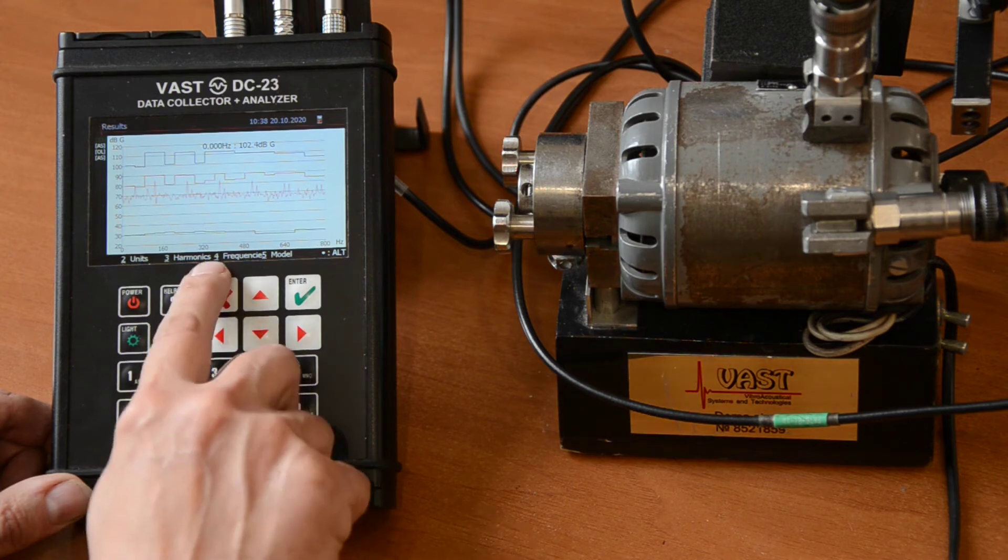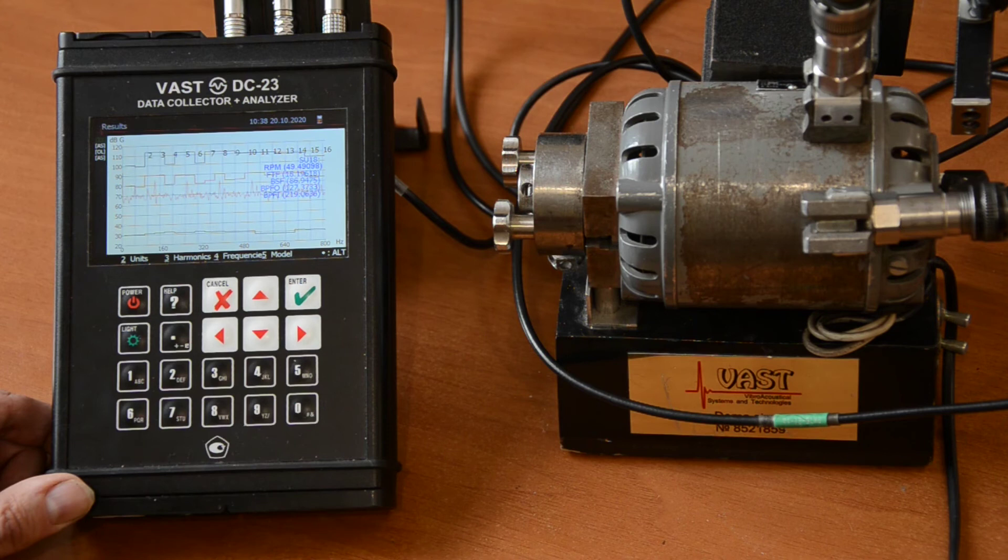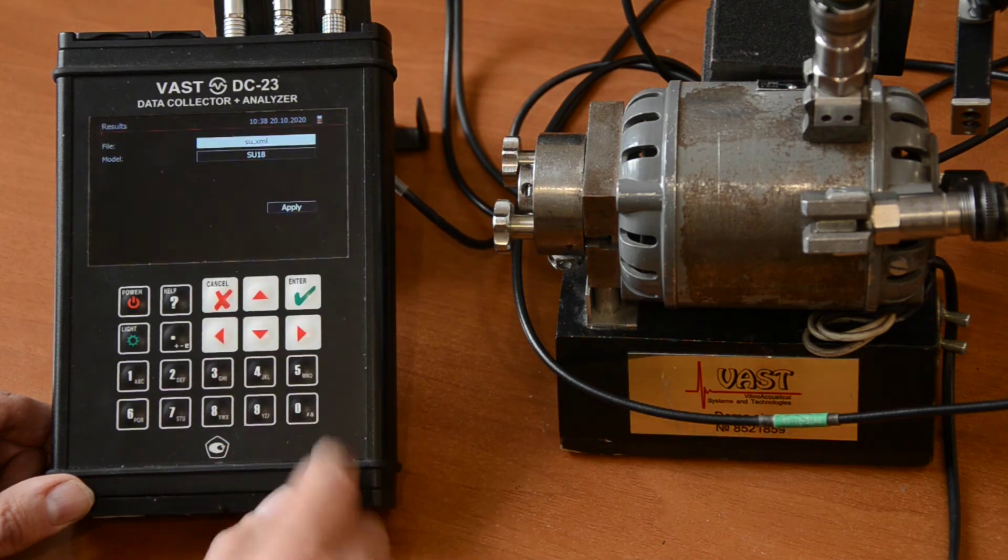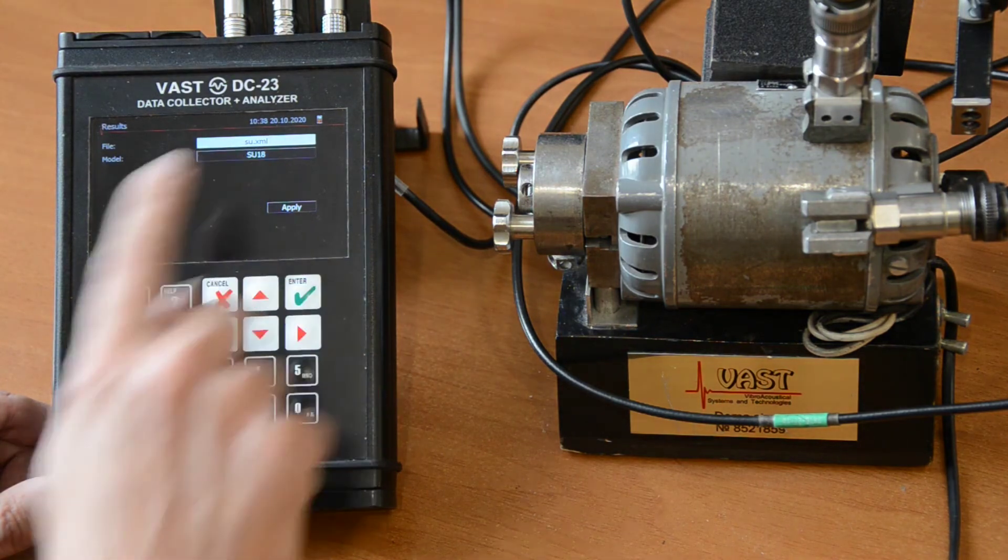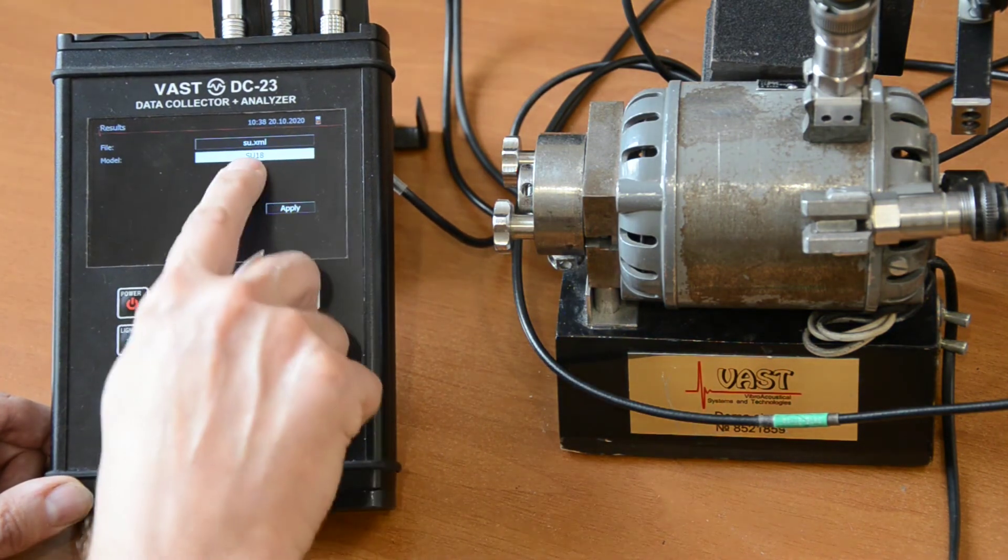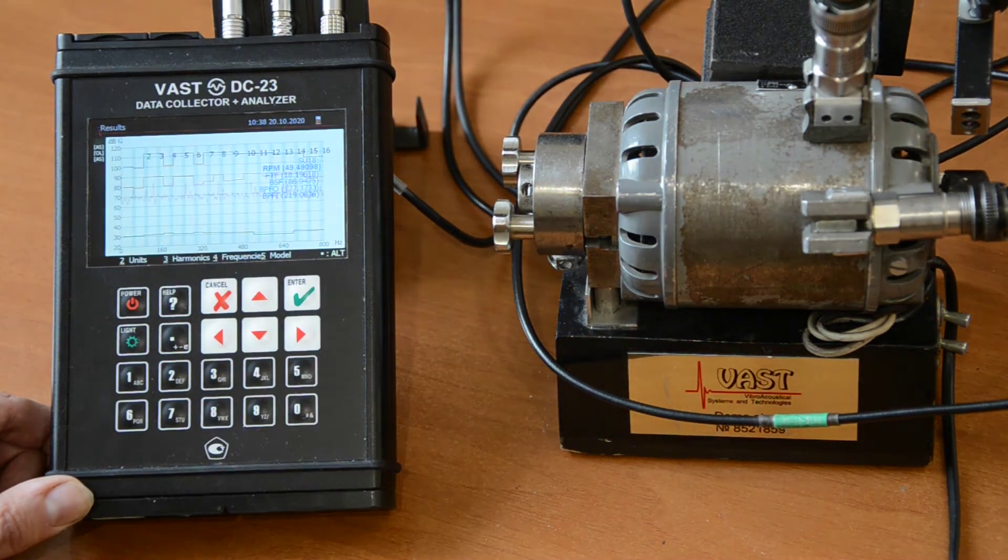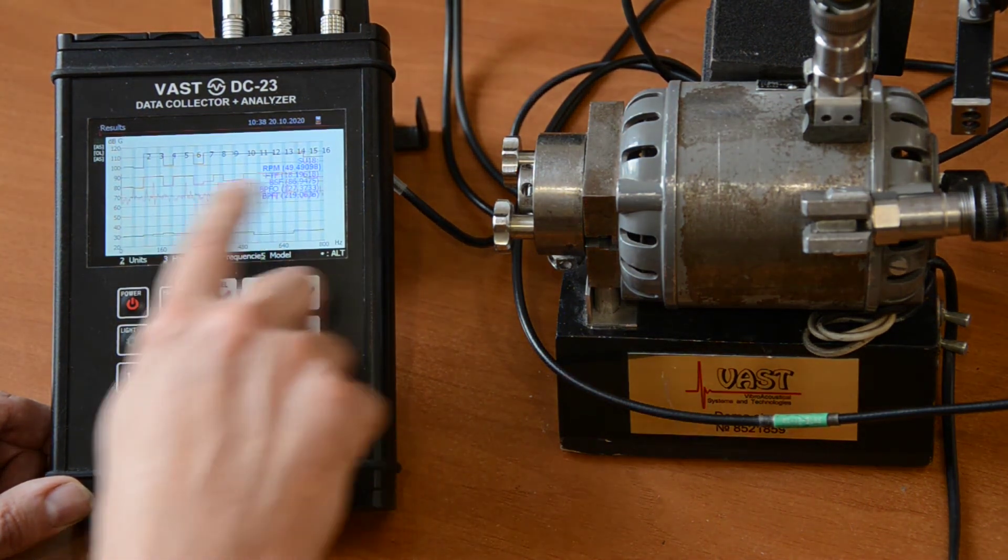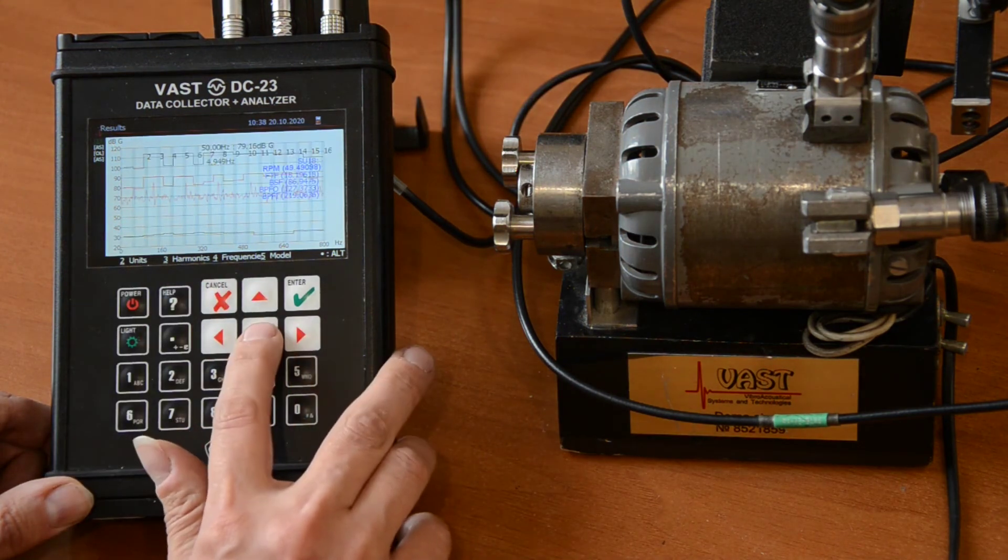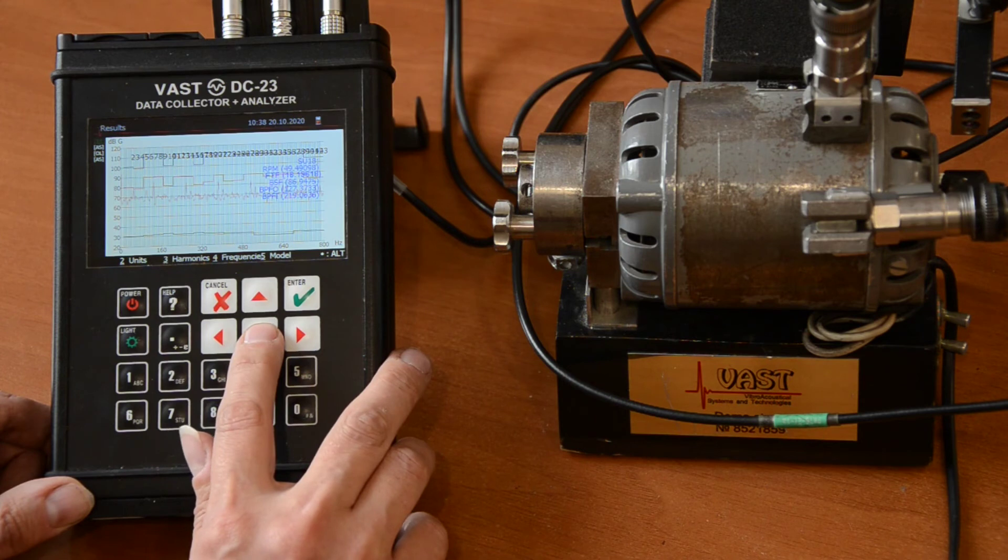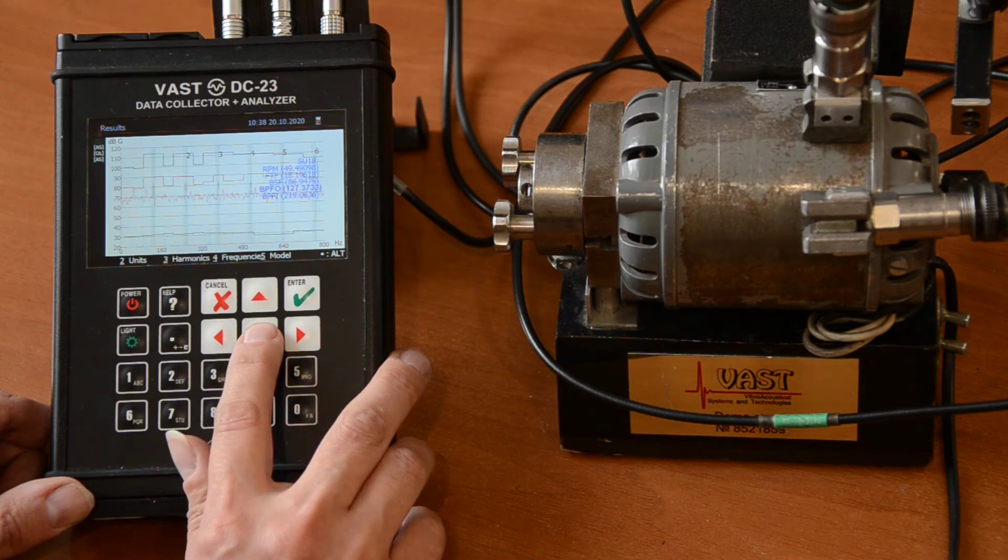This is the envelope spectrum. And we can go to the analysis mode. And look at the frequencies. We know the bearing. The bearing are in the model. Here. We have selected that from a file that we can download to the computer. We have selected the bearing type 18. Like this. And now we have RPM harmonic. We have cage harmonic. Not in there. We have ball spin frequency. Not in there. And we have BPFO. This is outer race.